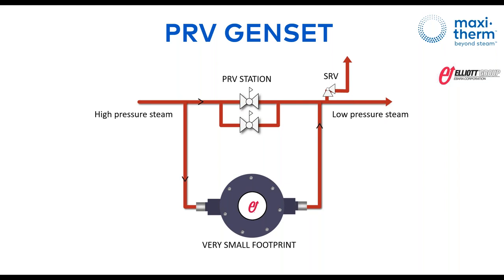So what we want to say on this picture, especially for retrofit application on existing PRV station, is you can keep those PRV as the backup. Remember, by doing so, you will still need 4% more steam at the inlet if you keep all the steam users afterward the way it is. But yes, the PRV station you can keep as a backup and put the turbine right underneath.